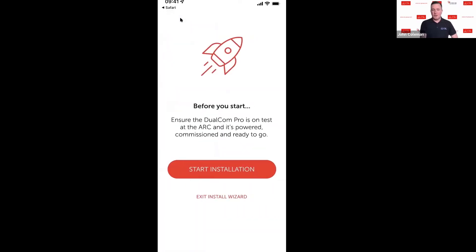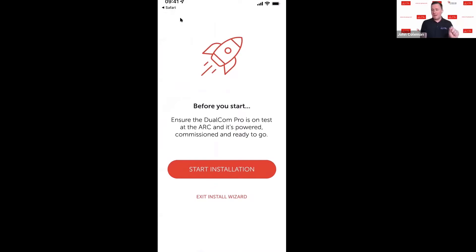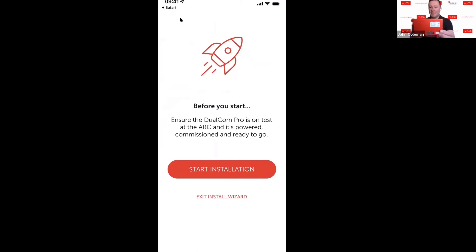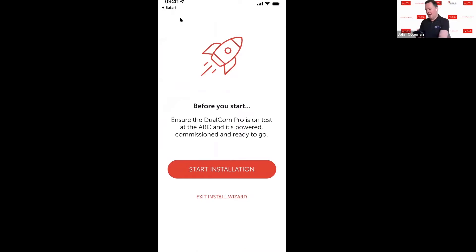So we're going to install a device. First and foremost, make sure that the device is on test with the ARC, make sure it's powered up, and also make sure that it's commissioned. To ensure that the device is commissioned, once you power it up you'll have the LEDs on the front here. Once you get the third LED on solid green, it means that the device is commissioned and is fully online.